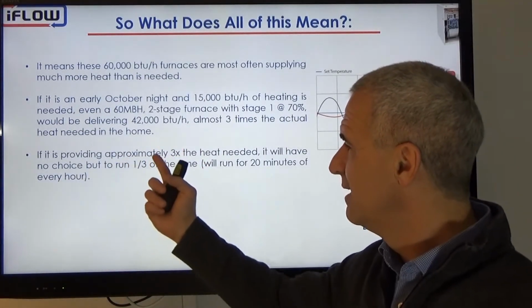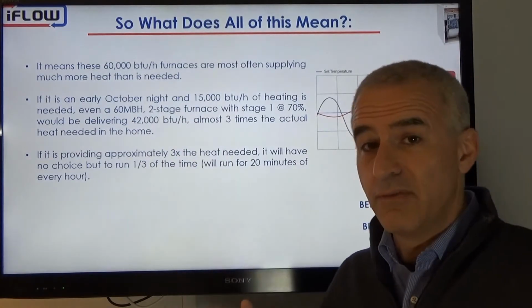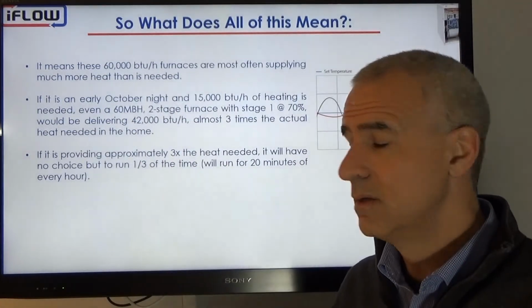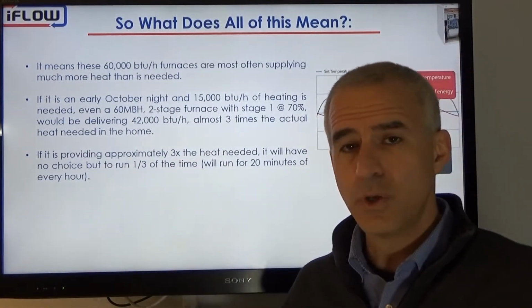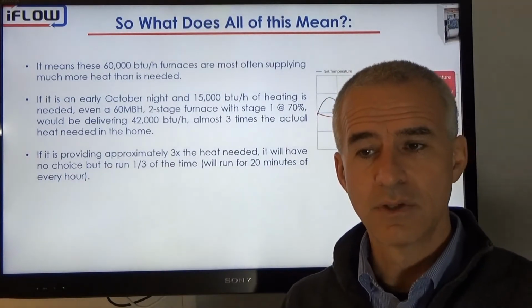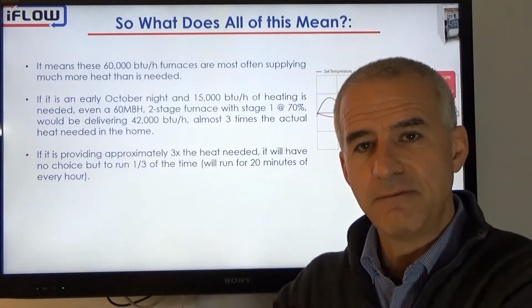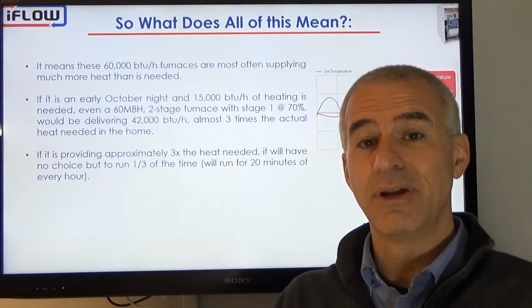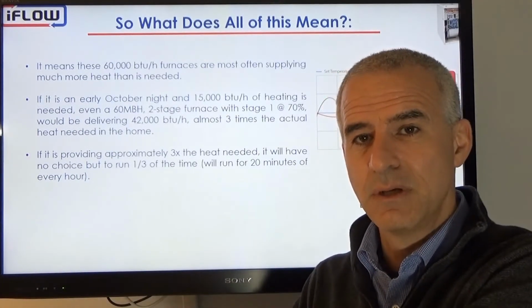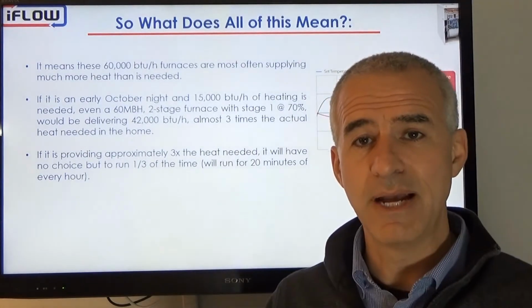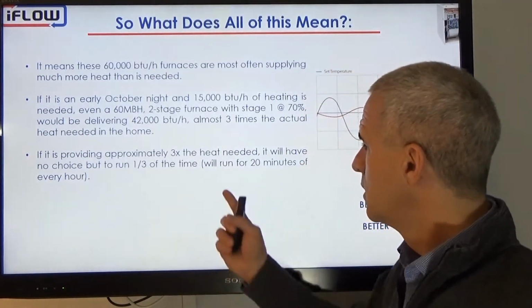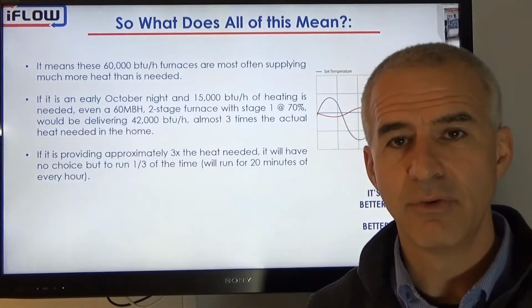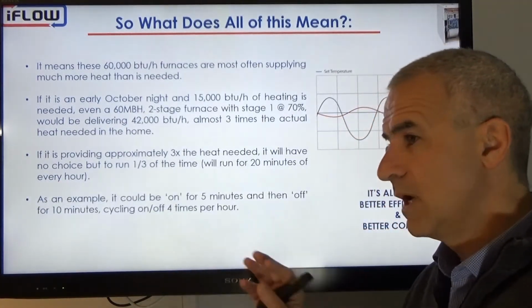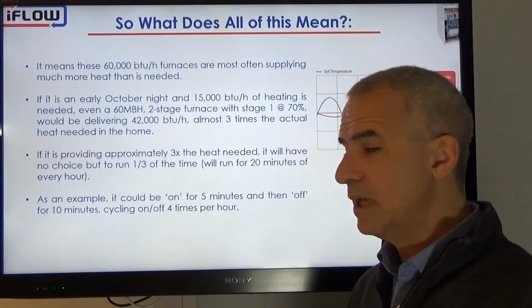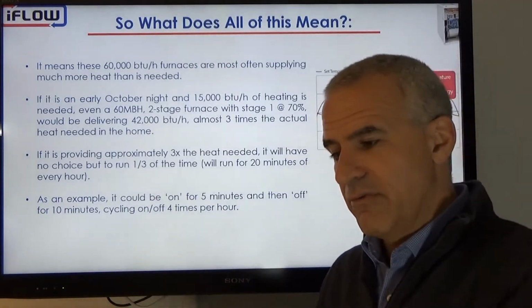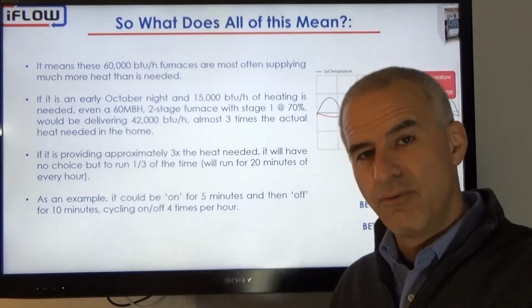So if I'm delivering 3 times the amount of heat when the furnace comes on at even stage 1, then I have no choice but to run 1/3 of the time so that I don't overheat the space, right? If I need 15,000 BTUs and I'm delivering 42,000, or almost 3 times, then I have to cut back and run 1/3 of the time. So it's going to run for 20 minutes of every hour. Now with the thermostat being what it is, it's probably going to be on for 5 minutes, then off for 10, and it's going to do that cycle 4 times each hour.